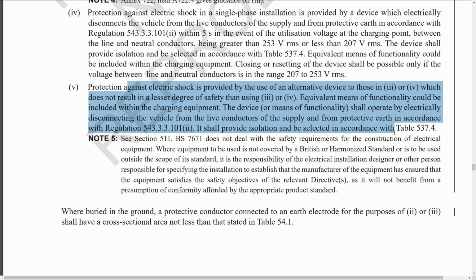And of course, again, with this, you will need to get details from the manufacturer to confirm that it does provide this degree of safety, and it is going to obviously operate in the particular instances given. So not a whole lot has really changed there. All it's done is saying that stuff that existed previously, and of course new stuff may be coming along, previously you had to note it as a departure, stating the manufacturer says this and this and this, and now you can say yes, it does comply, but you're still going to have to mention in there that the manufacturer states that it does in fact comply with this standard, that standard, or whatever else.